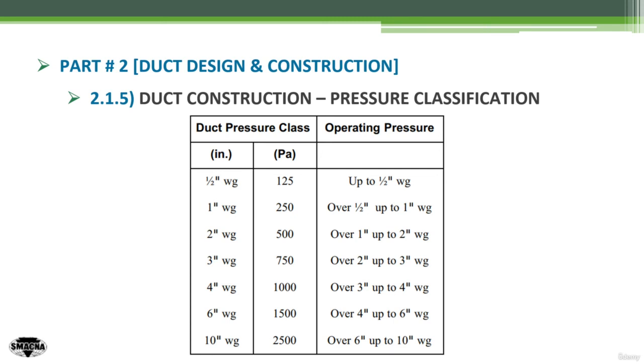If I have a fan with a pressure of 3.25 inches, I will go to the row from over three inch up to four inch, and I will choose 1000 Pascal or four inch as the duct operating pressure classification. This is the first input in the duct construction process table, which will allow you to bring further inputs including duct sheet metal thickness and other details.